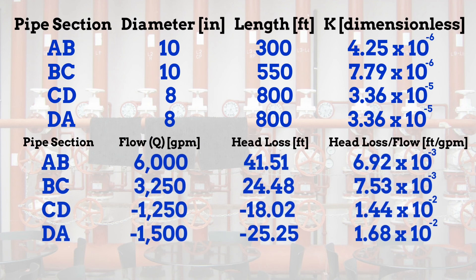Next, we take the current flow of each section of piping and calculate the head loss incurred in each section. The flow correction equation we will use is based on the adjusted Hazen-Williams equation, where n equals 1.85. Flows going clockwise in the system are used as positive values, while flows going counterclockwise are calculated as negative. Therefore, the flows for pipe segments AB and BC will be positive, while flows for CD and DA will be negative. We then find the values for each section of piping and calculate the flow correction.